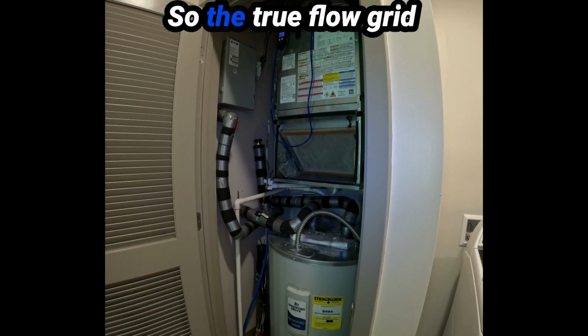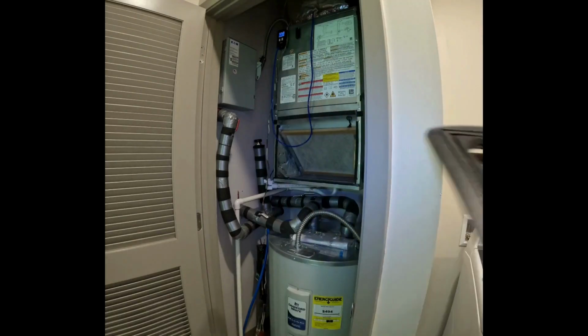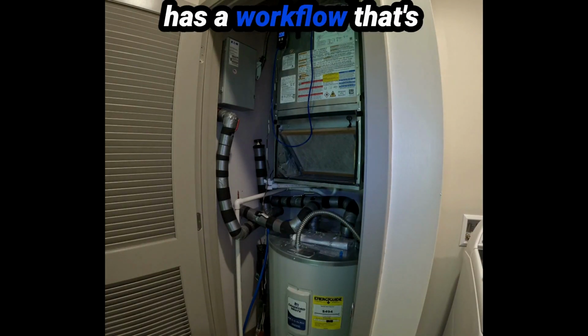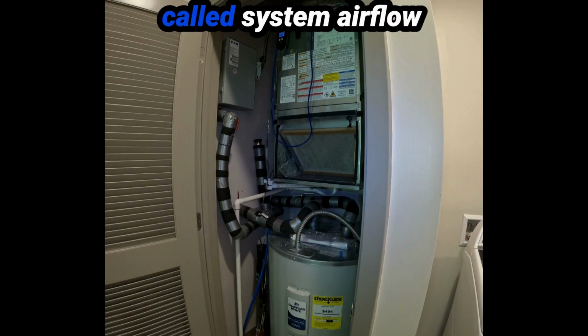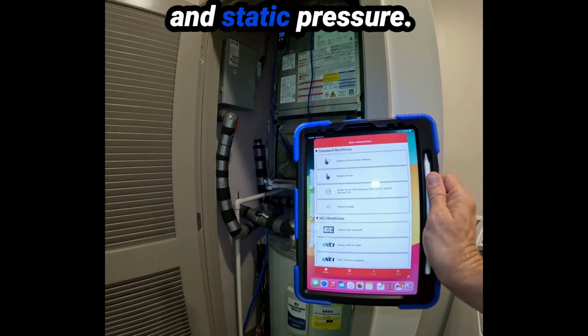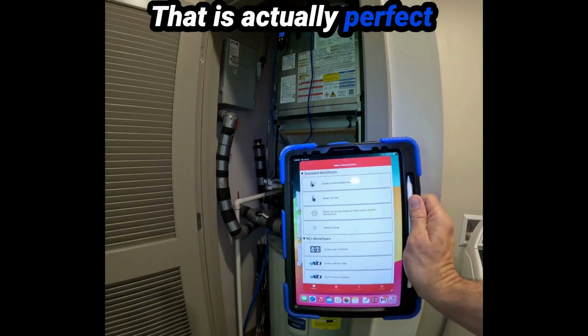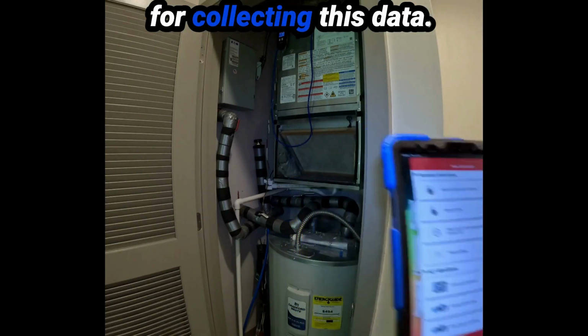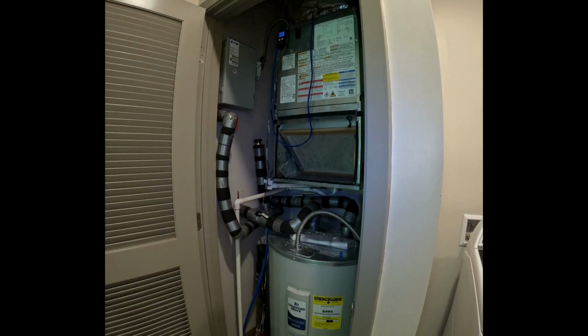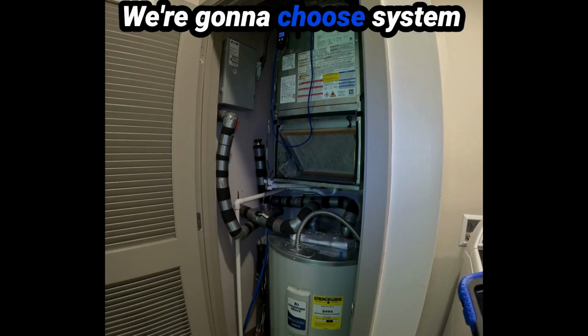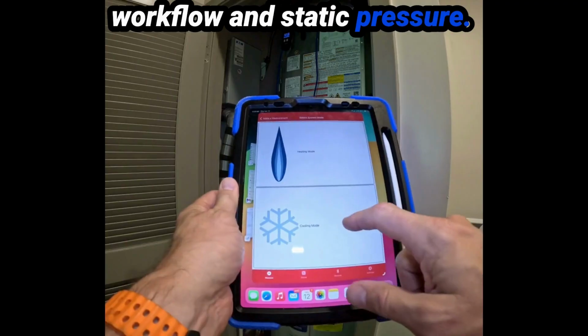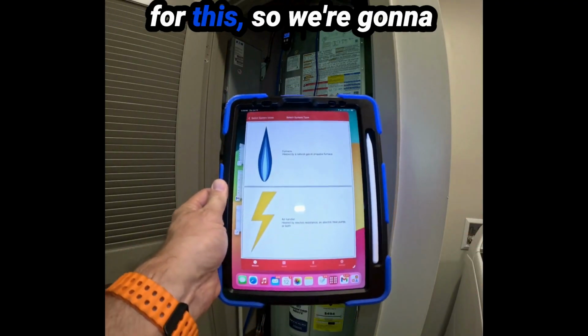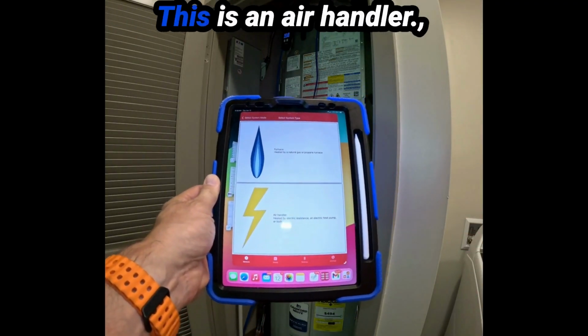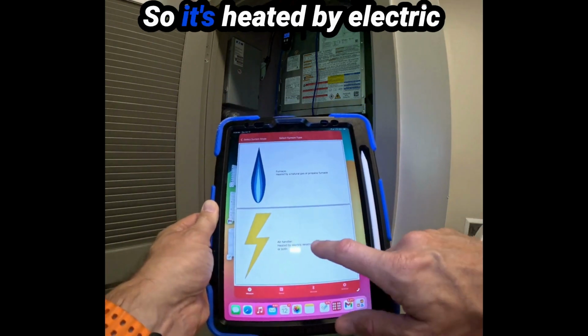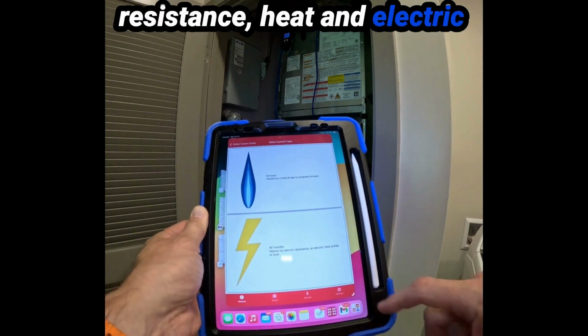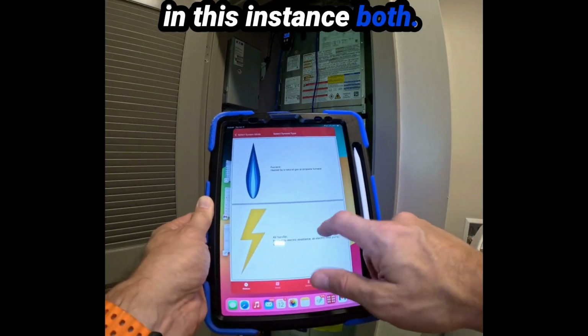So the TrueFlow grid has a workflow that's called system airflow and static pressure. That is actually perfect for collecting this data. We're going to choose system airflow and static pressure. We're in high cooling mode for this, so we're going to choose high cooling. This is an air handler. So it's heated by electric resistance heat and electric heat pump, or both, which in this instance, is both.